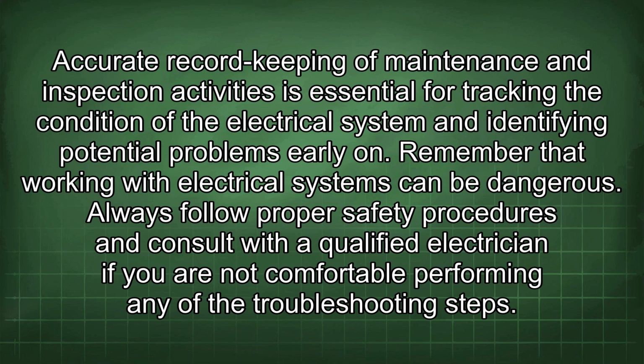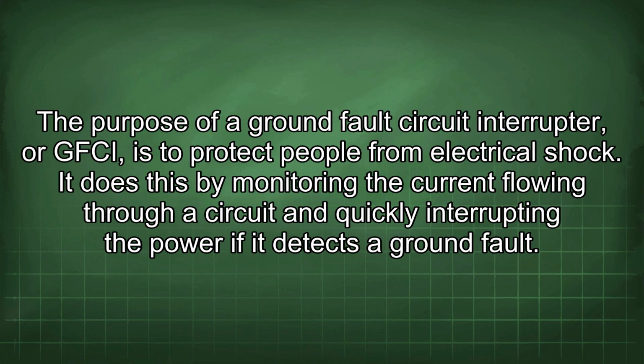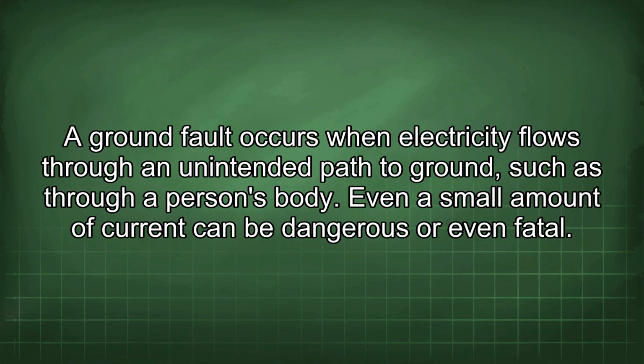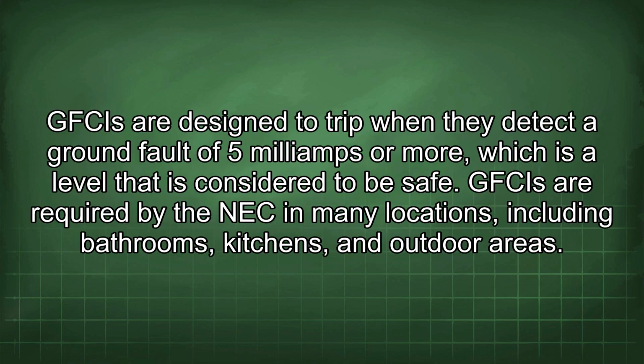The purpose of a ground fault circuit interrupter, or GFCI, is to protect people from electrical shock. It does this by monitoring the current flowing through a circuit and quickly interrupting the power if it detects a ground fault. A ground fault occurs when electricity flows through an unintended path to ground, such as through a person's body. Even a small amount of current can be dangerous or even fatal. GFCIs are designed to trip when they detect a ground fault of 5 mA or more, which is a level that is considered to be safe.